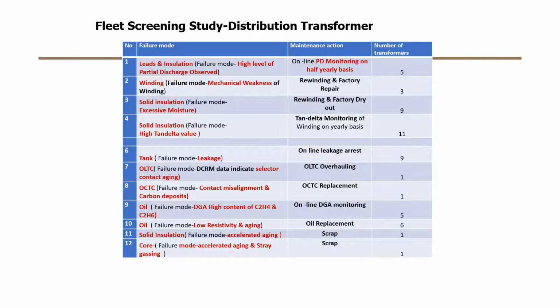Tank, already discussed. If there is a leakage, then you have to arrest the leakage. OLTC, if DCRM is indicating, in this case, that it was a selector contact aging, then OLTC overhauling is required. Suppose you don't do the overhauling, please don't operate the OLTC at least, because we know that on transformer failure as a subject, we have done a lot of projects on fleet management. We will show that. Bushing and the OLTC are the main components which initiate the failure of the transformer. So we have to be careful about the OLTC. An OCTC which we never operate, still it is in our system, and there is a chance of contact misalignment and carbon deposits. We find that in a lot of cases, because ultimately it's a part of the live circuit in a transformer. The component itself is a very low-end component, but it is a part of our transformer.